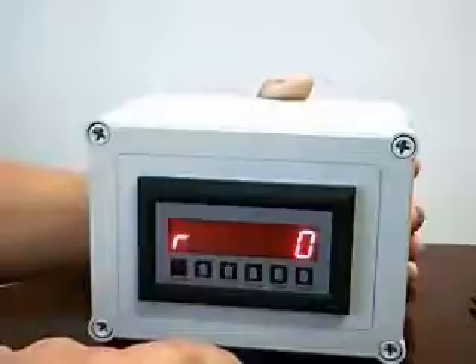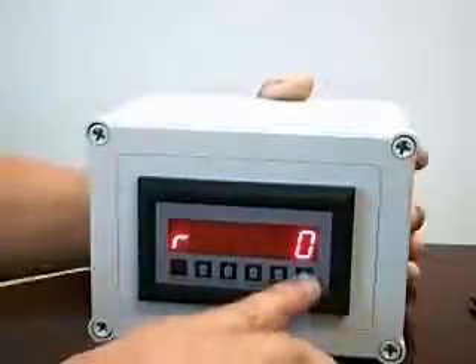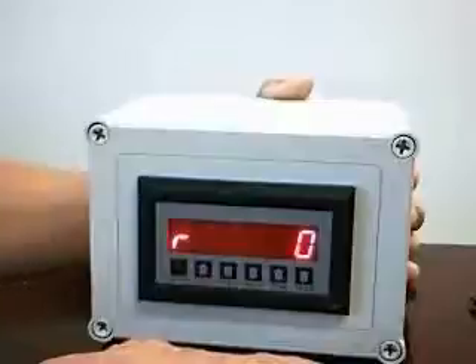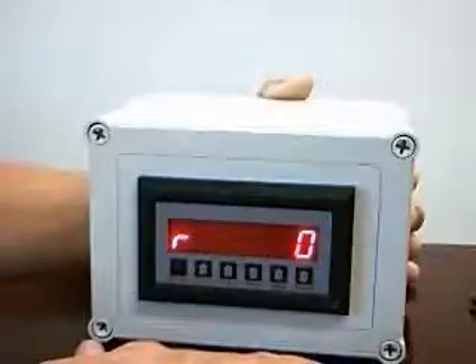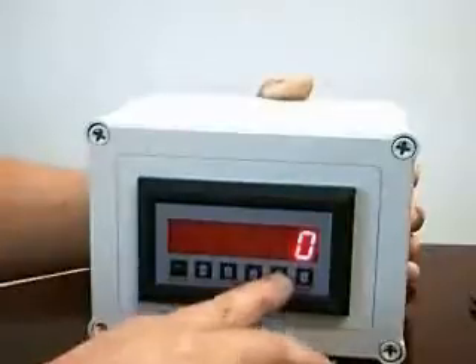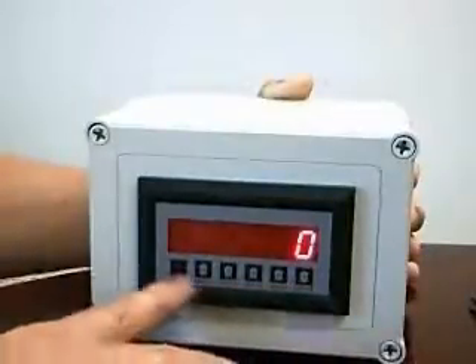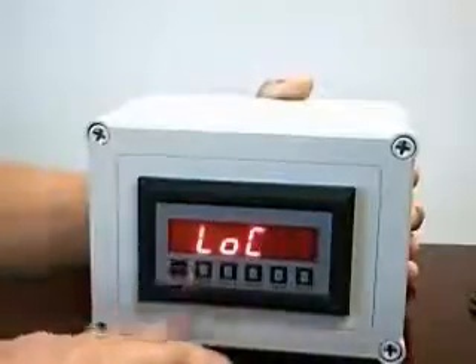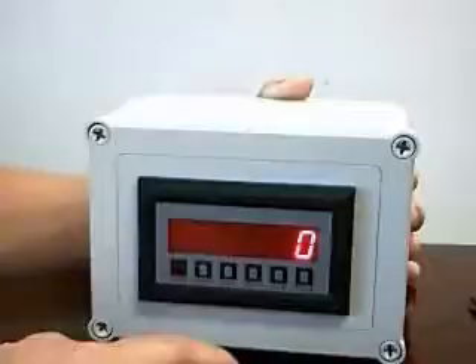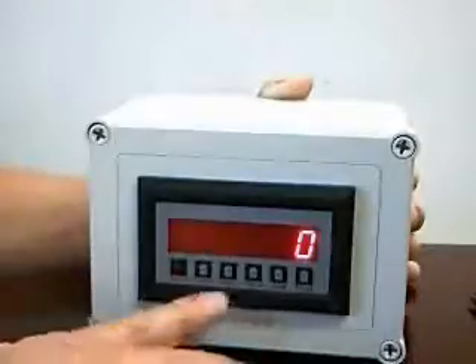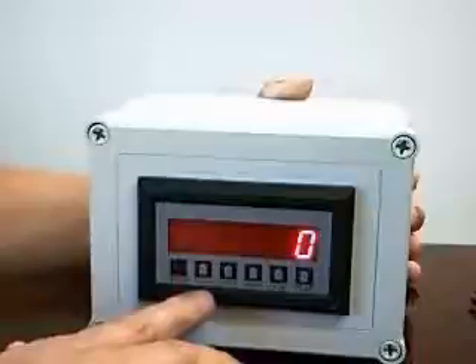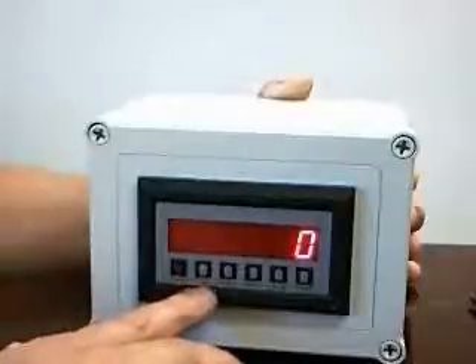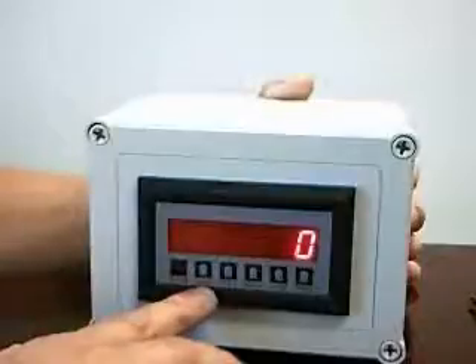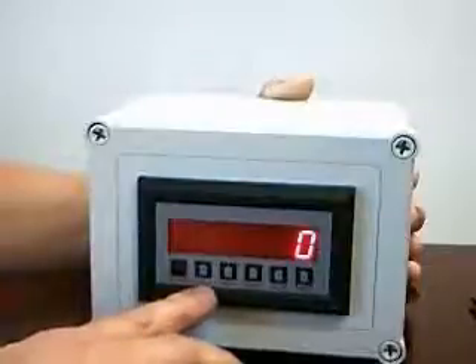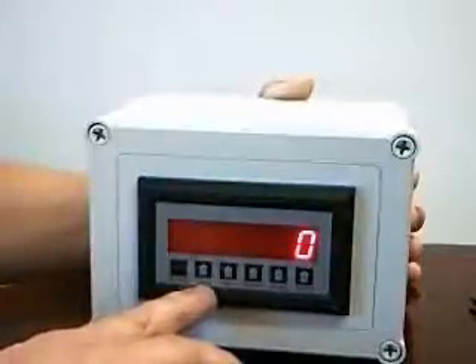Now you'll notice if I attempt to enter the program button, the display warns me that the unit is currently locked by password. Similarly, if while displaying the rate I attempt to reset it, it'll inform me that the unit is currently locked. One of our other buttons, therefore, is actually the unlock button and lock button. This works as a toggle. If the unit is currently locked, it'll unlock the unit. If it's currently unlocked, it'll lock the unit. So let's look at the operation to lock and unlock the unit.